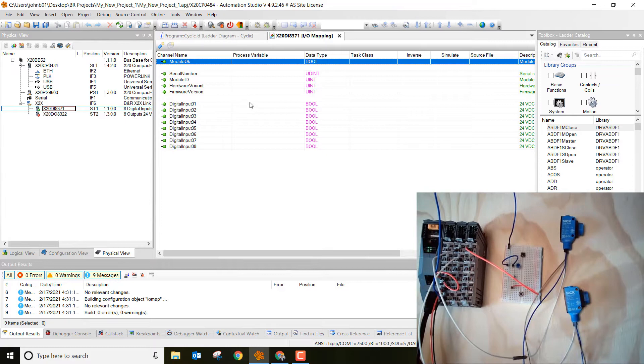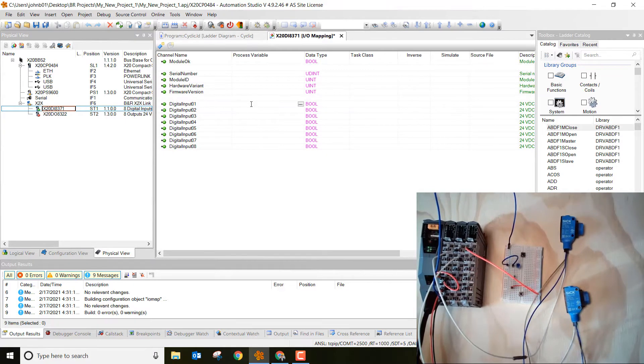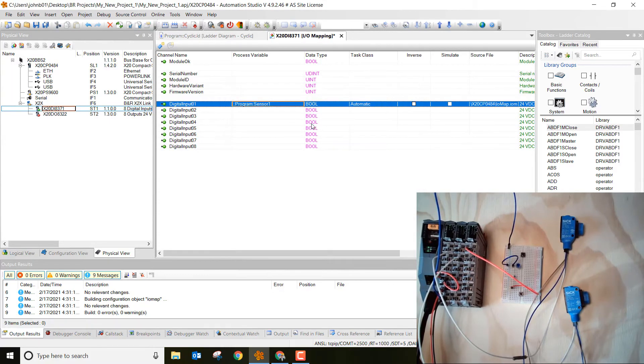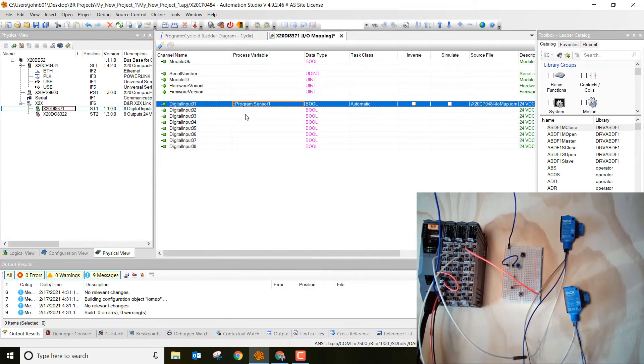So let's go to digital input 1, double click in the white space right next to it, then click on the three dots. Then what we want to do is open up program and double click on sensor 1. All right, we mapped sensor 1, the sensor 1 variable, to digital input 1.